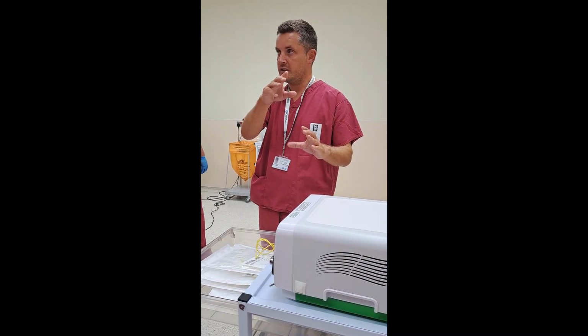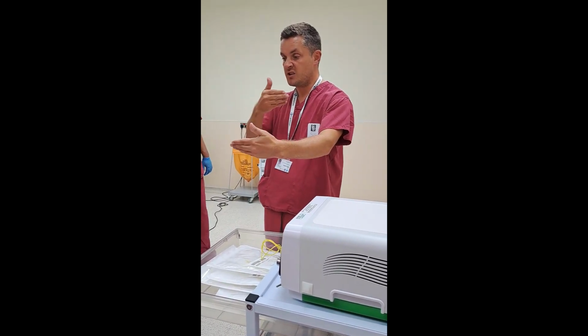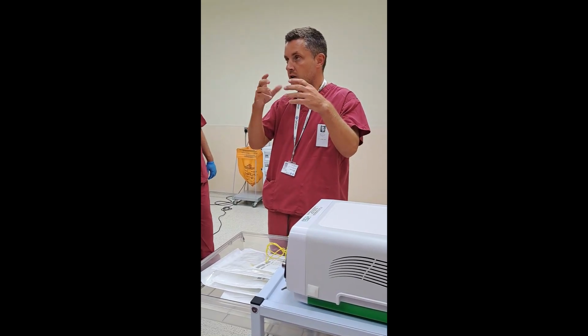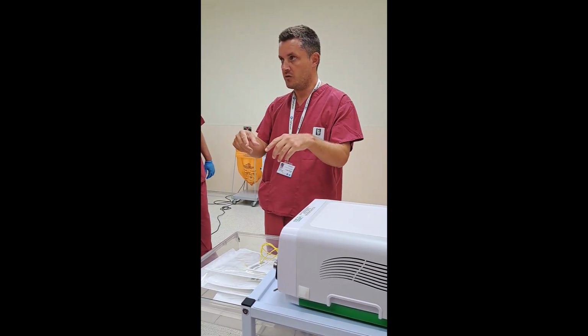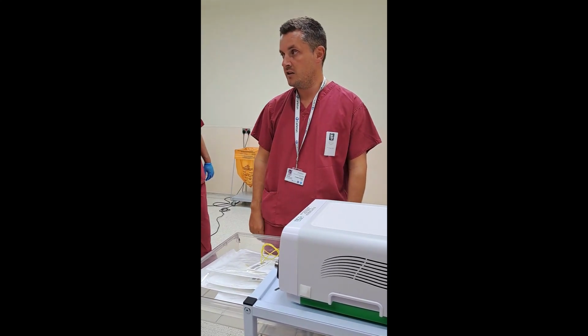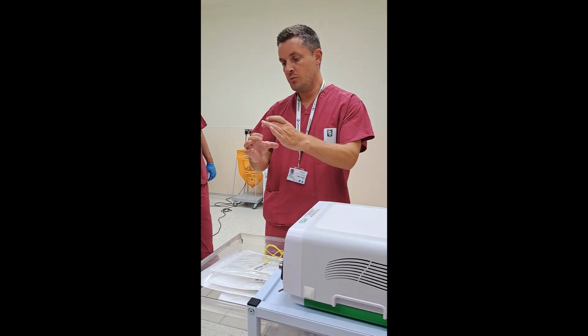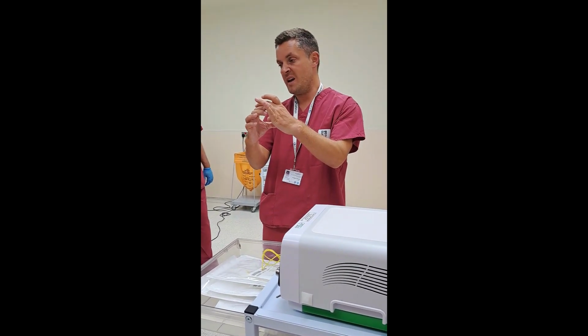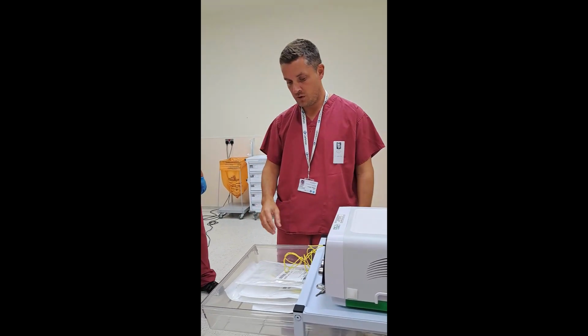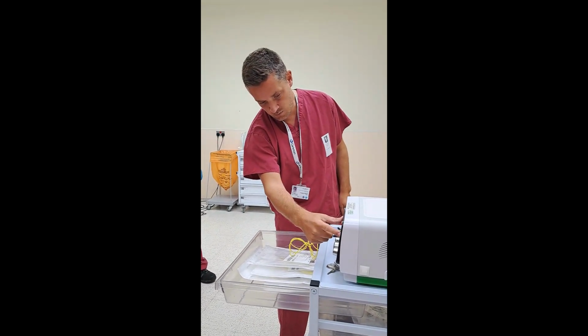So for a CO2 laser, because you have just a physical barrier between you and the laser, the user doesn't need to have a pair of goggles in the microscope. There's no filter. But for this one, you do have to have one in the operating microscope. They normally just remain in there the whole time. The glass looks clear, but it does actually block the wavelength. So the system just asks you if you've got that.